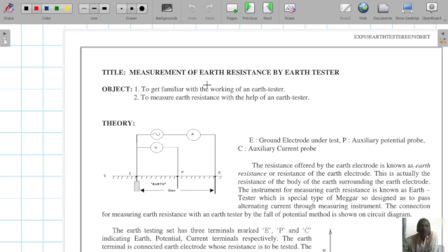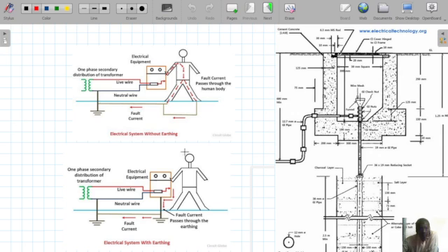The name of the experiment is measurement of earth resistance by earth tester. Now first of all we have to understand why earthing is required, and to understand that, let us take this figure. Now here is electrical equipment. The supply is given to that equipment from the secondary of a distribution transformer. So this is a neutral wire, this is the live wire, and in this system there is no earthing.